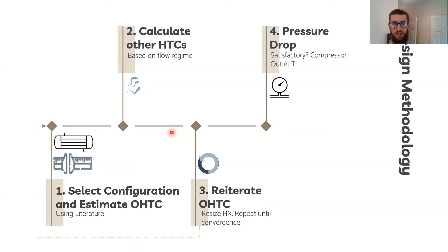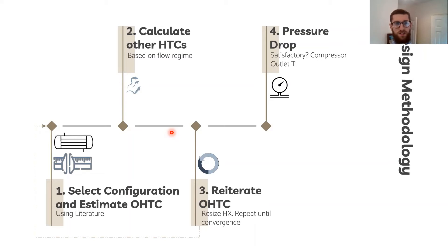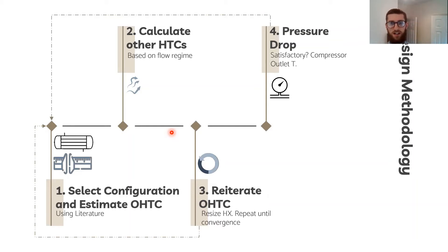Once that converges, the pressure drop is calculated. My pressure drop was much too high, and so I needed to change the design of the heat exchanger, which again changes the flow regime and that changes the overall heat transfer coefficient again. It starts a new iterative process.